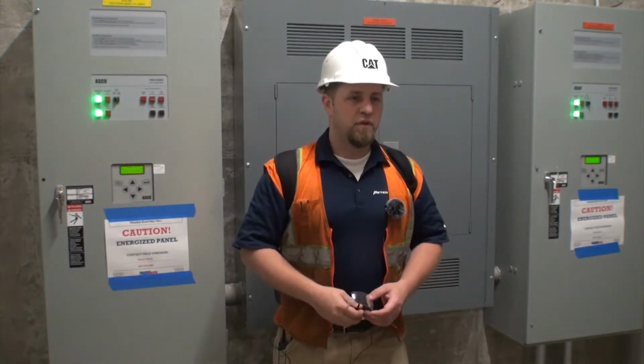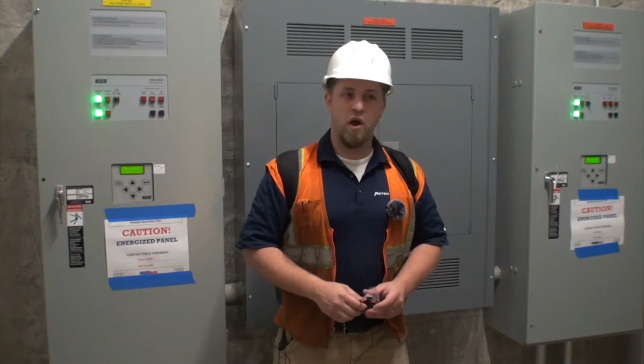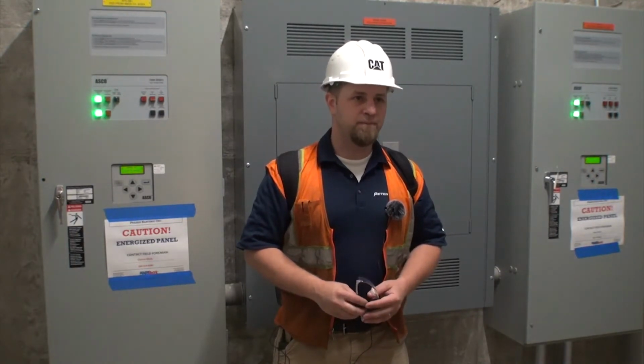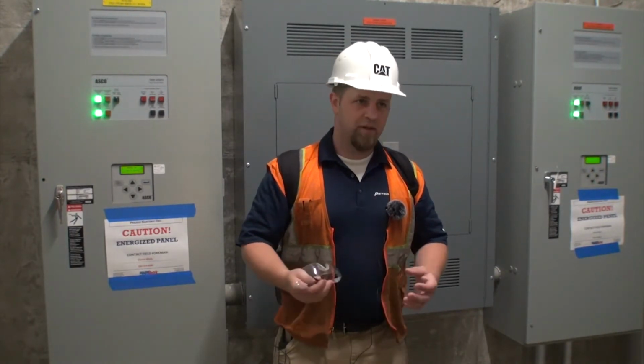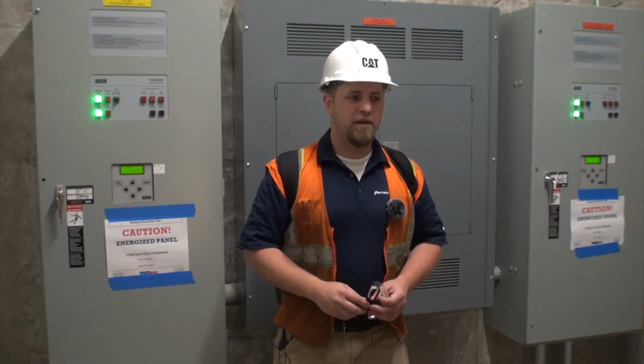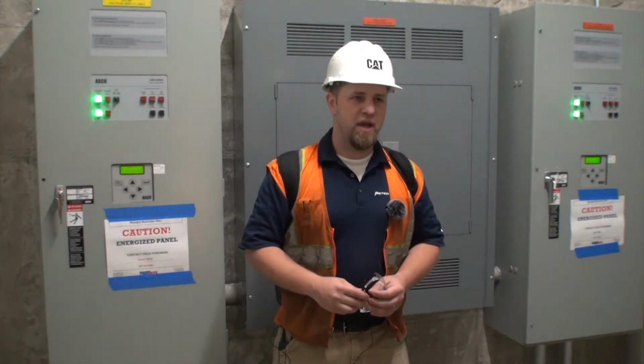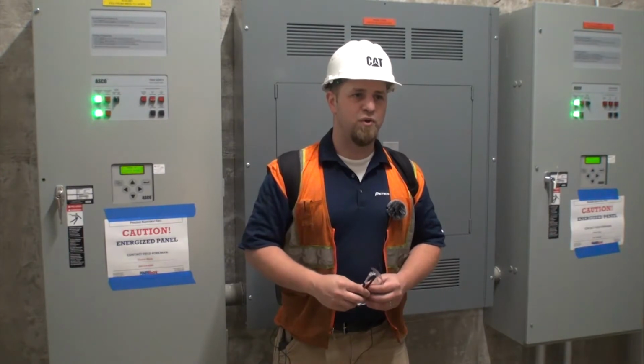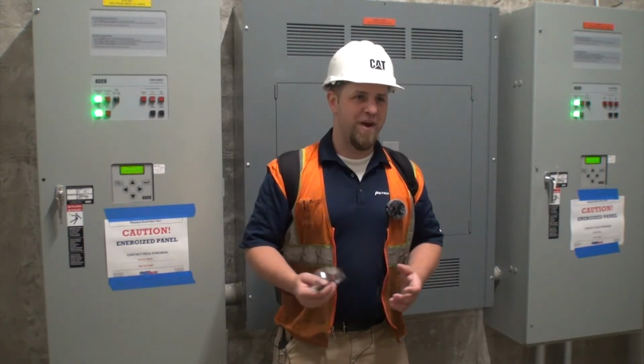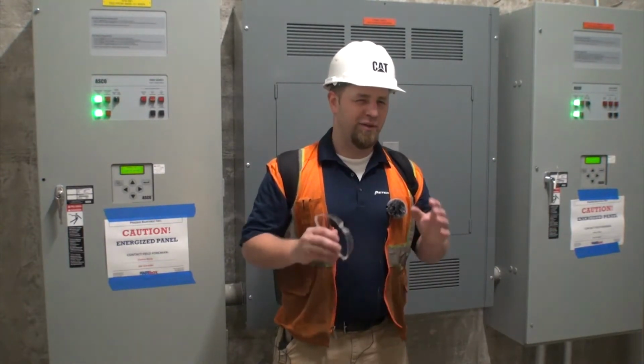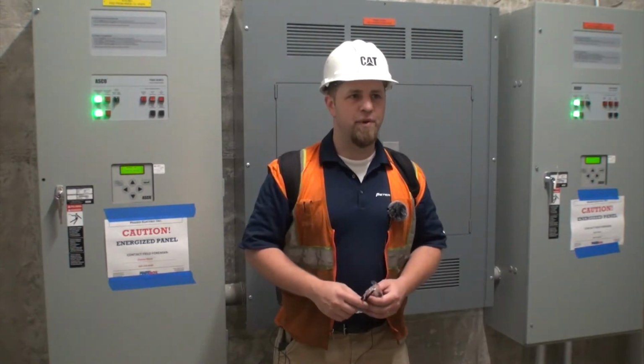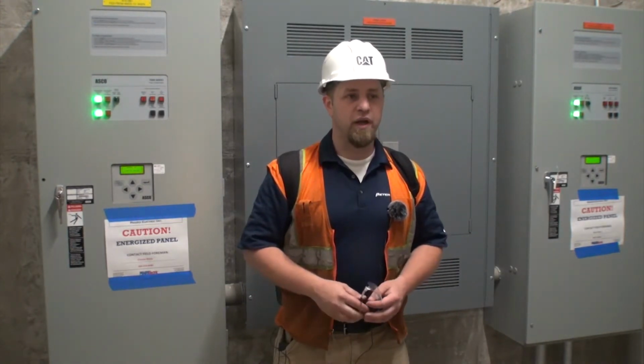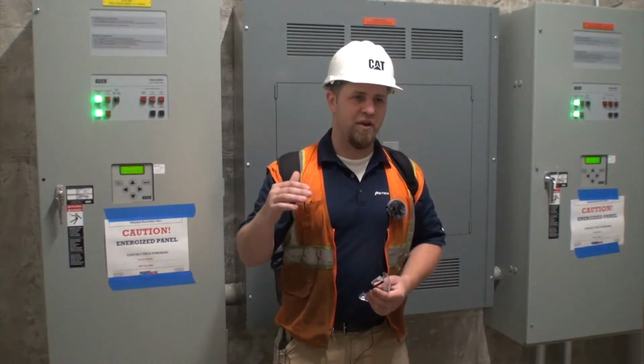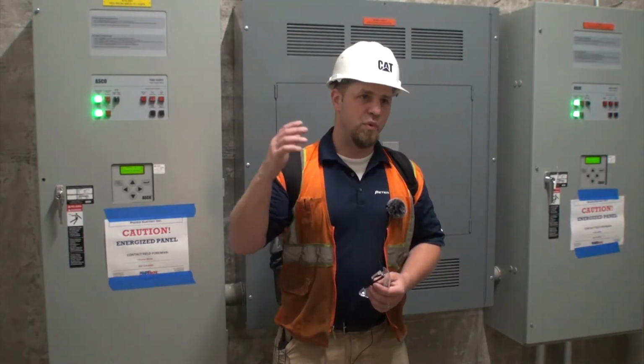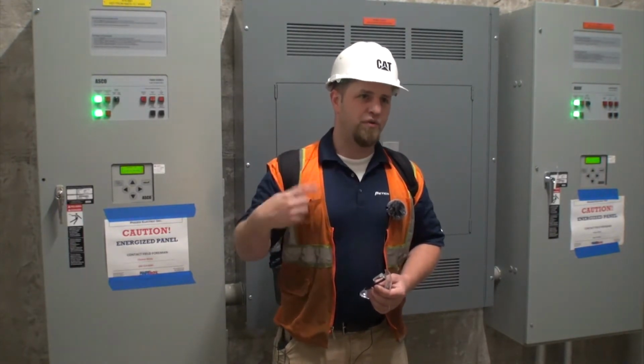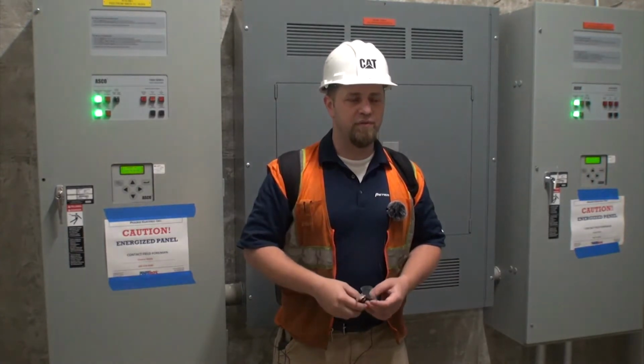So it doesn't run on a temperature cooldown? No, it's just a 5-minute cooldown on those. I got it, it runs until it gets to a certain temperature and then shuts down. Yeah, I think the reason Cat doesn't like to do it that way usually is because if you had low coolant or bad thermostats, you're relying on something that might be a little off. But it does work, as long as you're getting the temperature back down, you're letting the turbo spool back down. You got the oil going through it, that's the main thing they're looking for.